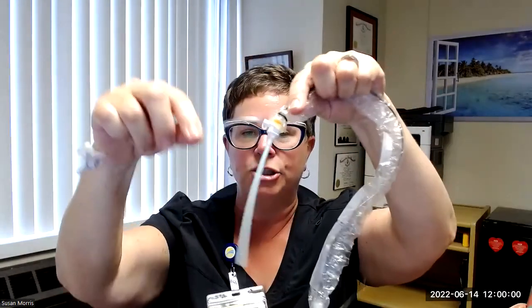When we look at this device, so here is my sheath or introducer. I will have an intravenous infusing over here, just maybe saline or dextrose at a minimum of 20 mils. And my stopcock will be in the open position, and the air will be removed from the syringe. So there will be no air in the balloon when it is in the patient.